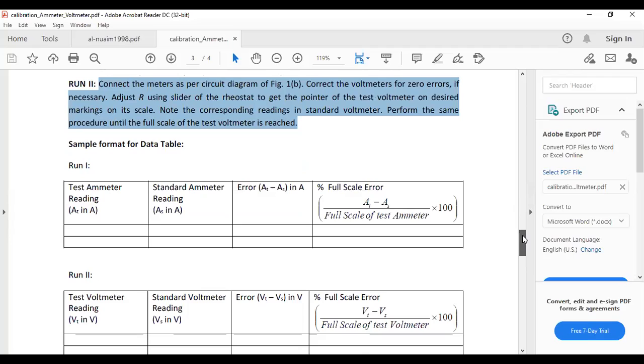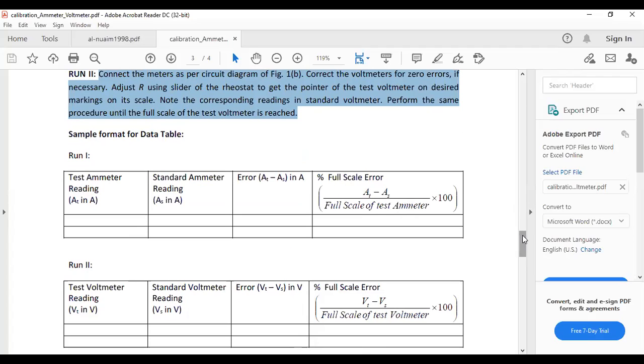Okay, so therefore in the table also we have the test ammeter reading in the first column, because that is the independent variable here. Then the standard ammeter reading. Then we'll calculate the error like this: the test minus standard. So that is the error. Okay, error can be negative, error can be positive. And the percent full scale error is calculated like this. That is the actual error divided by the full scale reading of the test ammeter.